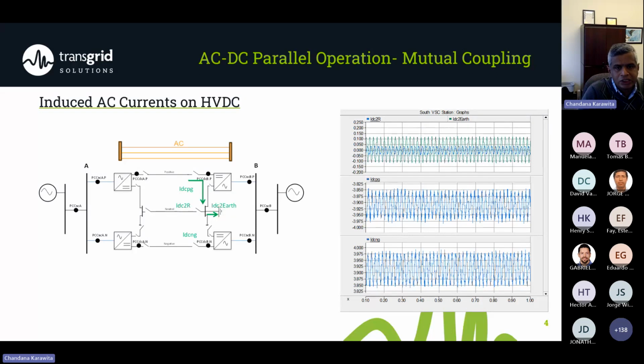One of the main challenges with AC-DC parallel operation is the mutual coupling. We all know about this magnetic coupling between DC lines and AC lines. One issue is the induced AC currents on the HVDC. When we have high voltage AC transmission parallel to the DC transmission, we see that on the DC lines a 50 hertz or 60 hertz component appears.